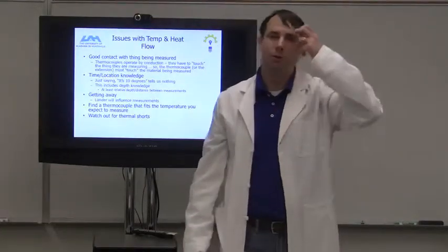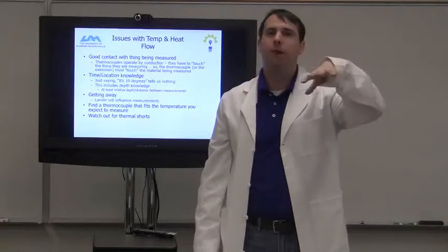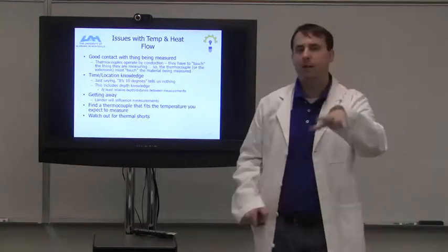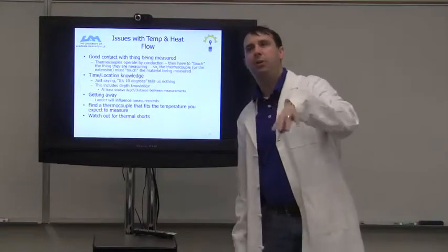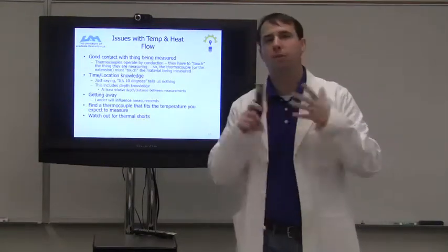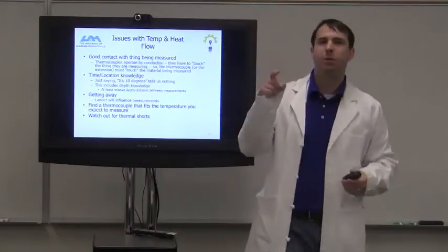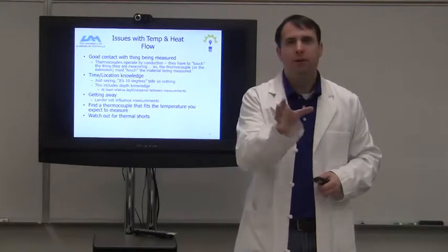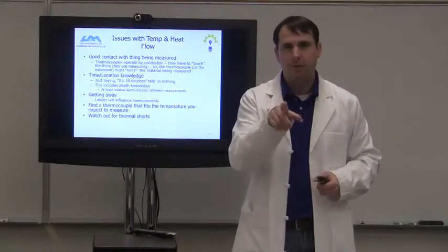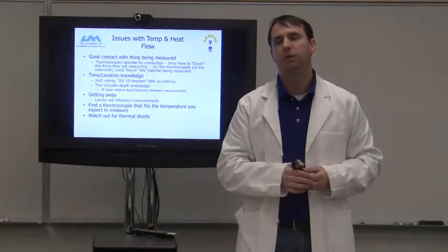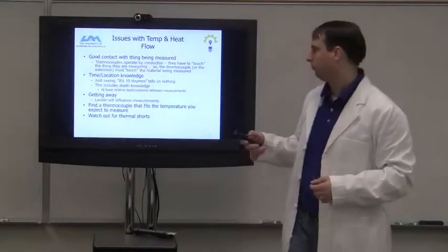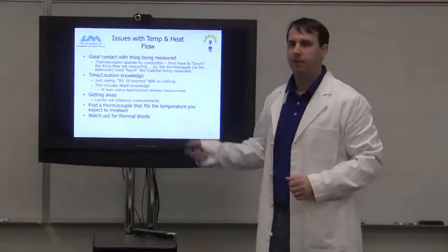You want to watch out for thermal shorts. Watch out for conducting heat from areas that you don't want to conduct it to areas, you know. So just pay attention to what you're measuring and what is around what you're measuring. If you're measuring temperature and your thermocouple is in the middle of a big chunk of metal, the big chunk of metal will also affect the measurement of that thermocouple, that temperature. So be aware of that. That's a design thing we'll talk about later as we get closer to design stuff, but I just wanted you to be cognizant of that and start thinking about it right now.